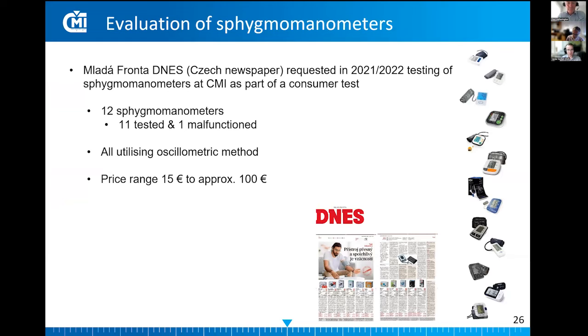In 2021, after the advanced oscillometric signal generator was already developed within our project and was being tested at the University of Ljubljana, we were contacted by the local newspaper Mladá fronta Dnes, who wanted to perform a consumer test of sphygmomanometers. They were hoping it would be non-problematic testing of 12 sphygmomanometers, all utilizing the oscillometric method, within a lower pressure range.